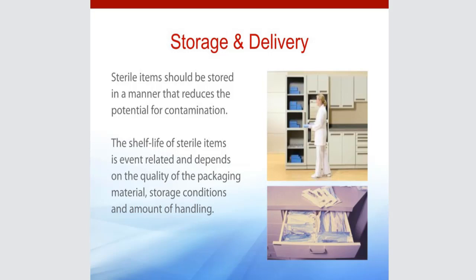When we do store, we said that it's better to have them in a cabinet. If you're using cassettes, please store your cassettes up on edge so that when you go to remove them, you're not pulling one out that's underneath two other ones, because there's too much weight and you could end up tearing the paper. You also want to abide by a stock rotation principle that's going to be based on your sterilization date. So it's first in, first out. So if I had an instrument package that I put in on October 1st, and I had another one in there that went on October the 12th, I'm going to use the October 1st one to keep my instrument rotation going.